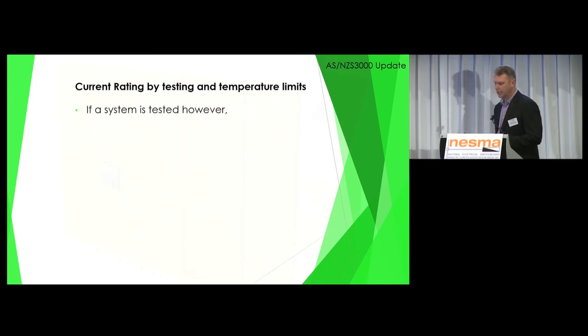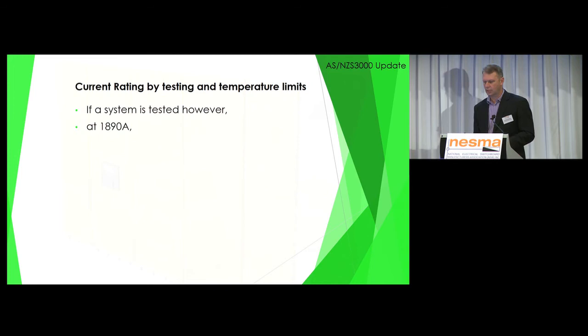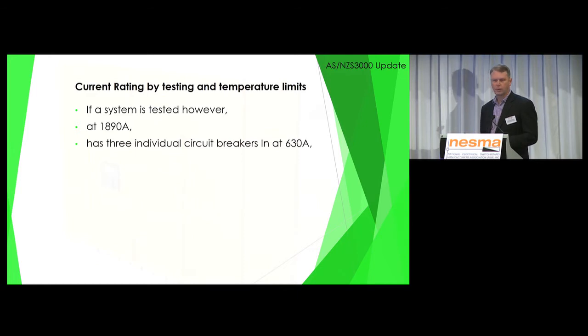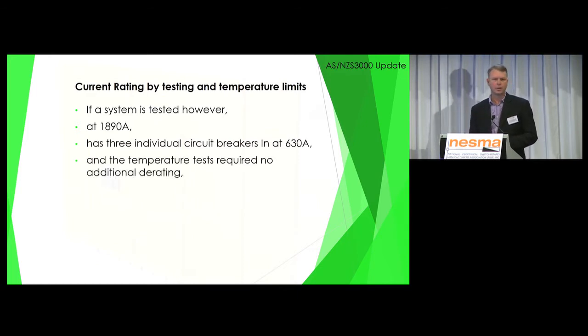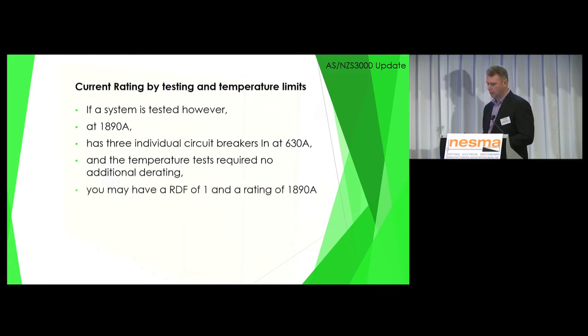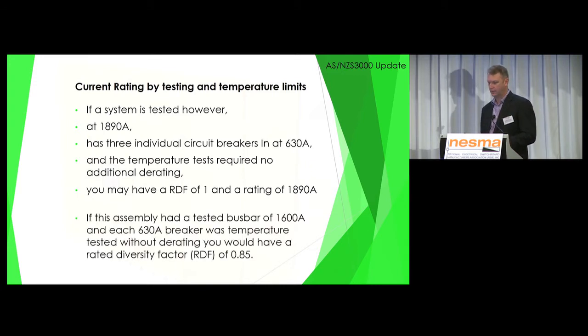So if a system is tested, let's call it 1890 amps, has three individual circuit breakers at 630 amps. These have been temperature tested and require no additional derating. And we may have a rated diversity of 1 because we've got a main bus of 1890 amps. There's no reason why we haven't got a rated diversity of 1 and a fully rated system.